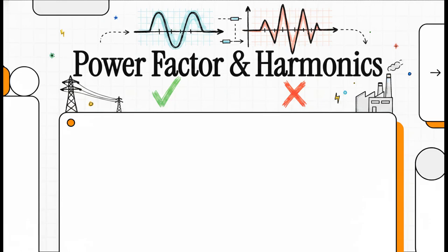Okay, let's jump right into this explainer and shatter a pretty dangerous misconception right out of the gate. A lot of folks think steady-state voltage compliance automatically guarantees a healthy grid. Like, for anyone managing high-voltage operations, you might think as long as your voltage readings fall within their legal bands, say that plus or minus 6% tolerance on a 66 kilovolt network, you're perfectly fine, right? Well, absolutely not. That is literally only half the story.